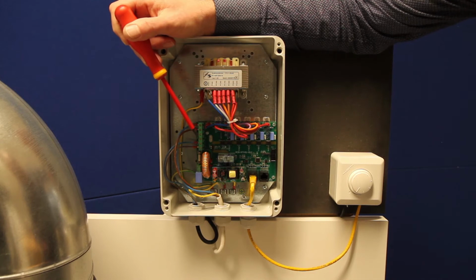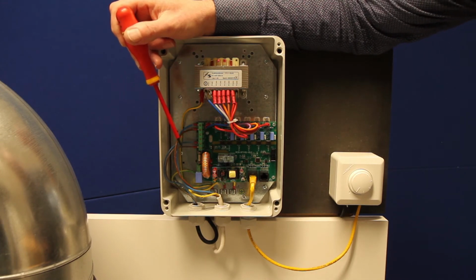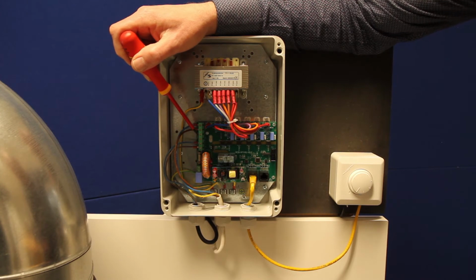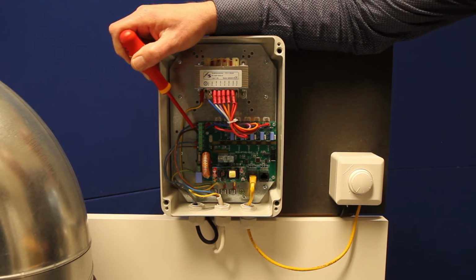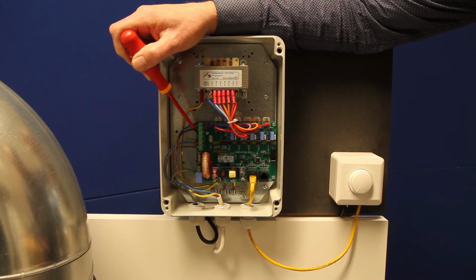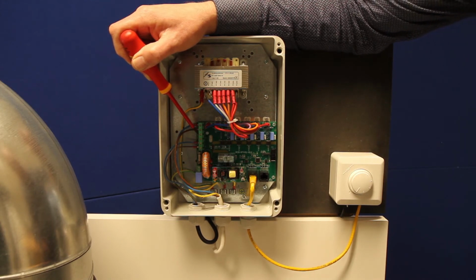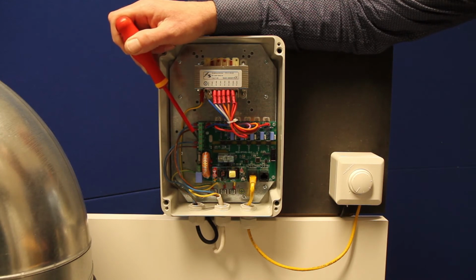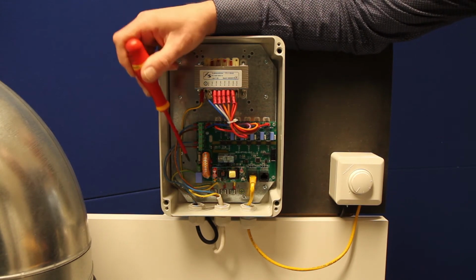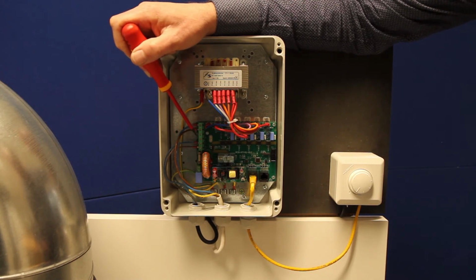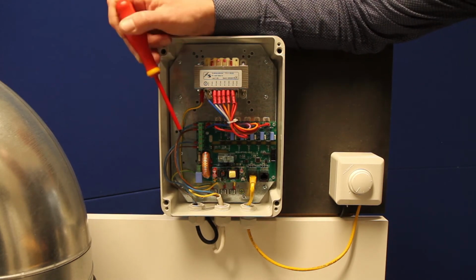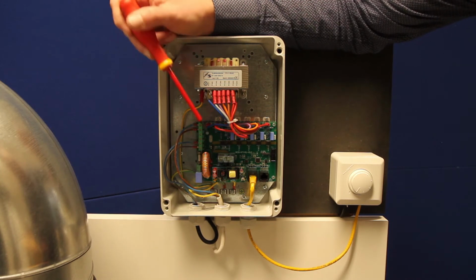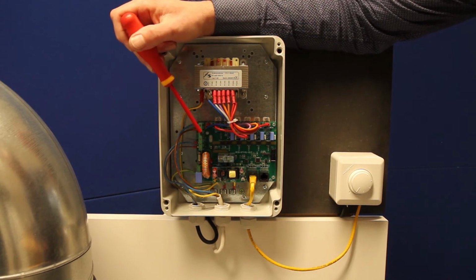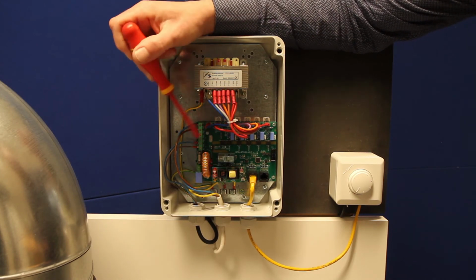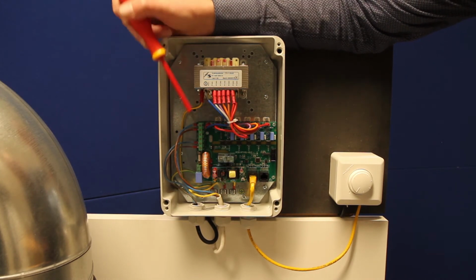Since this controller has intelligence on board through its Modbus registers, you have many more options. For example, you can reverse it so that the 230 volts is applied to the unregulated output when the regulator is in the 0 position, or when it provides power to the motor, or when a TK alarm comes in, so that you can, for example, operate a warning light or a buzzer. There are several more options for controlling the unregulated output. I am thinking of overload, overcurrent, overtemperature inside the unit, and so on. All things that the logic will perceive and with which you can control this unregulated output.